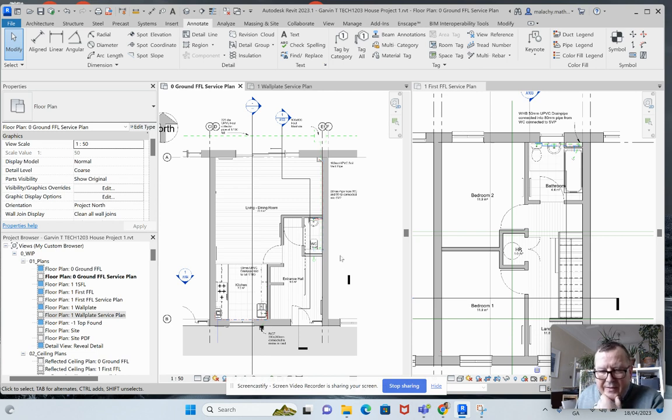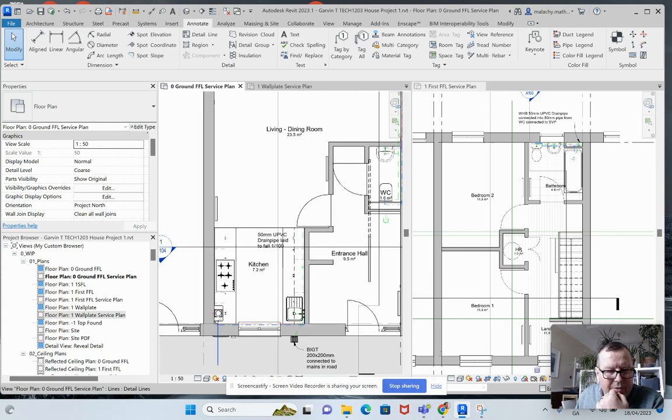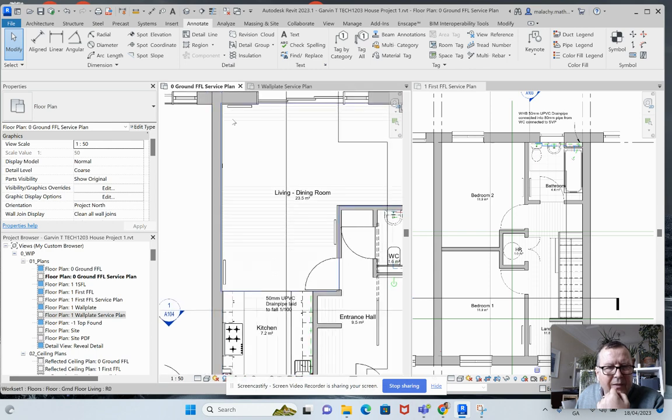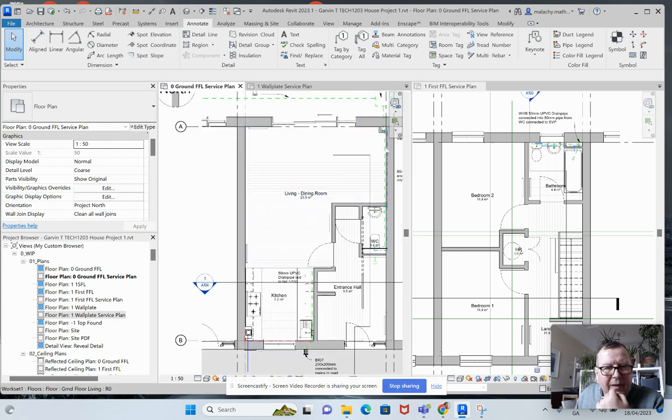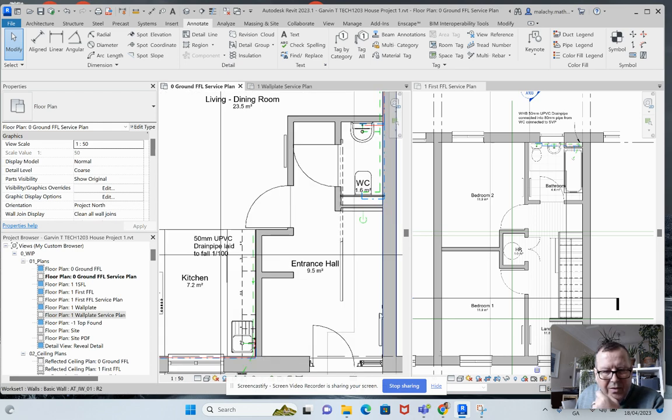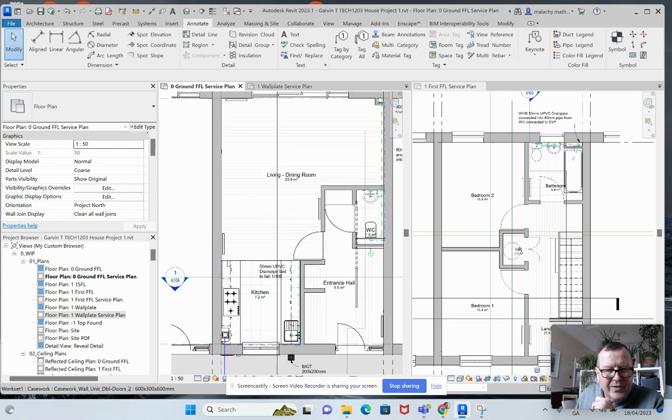Generally, what happens here is that it's not an individual supply, so it'll come from there, go to that radiator, to that radiator, come across then here and supply that radiator, supply that one. So it'll come into it and then it'll go out of it, and that's the flow and return element. Now it's done by double pipes. So first of all, we'll do the hot, that'll go all the way around, and then we'll do the cold, that'll go all the way around and back here.